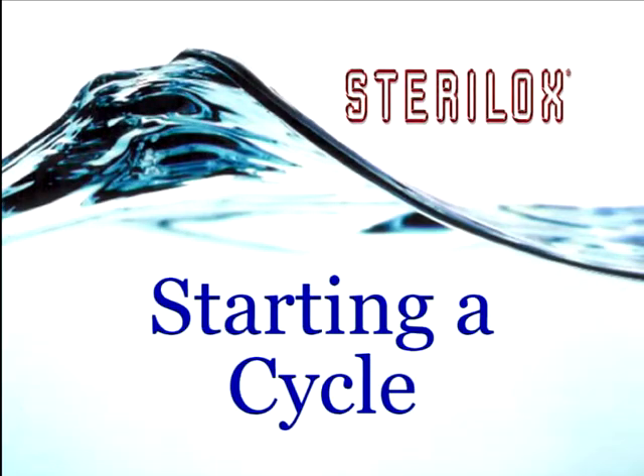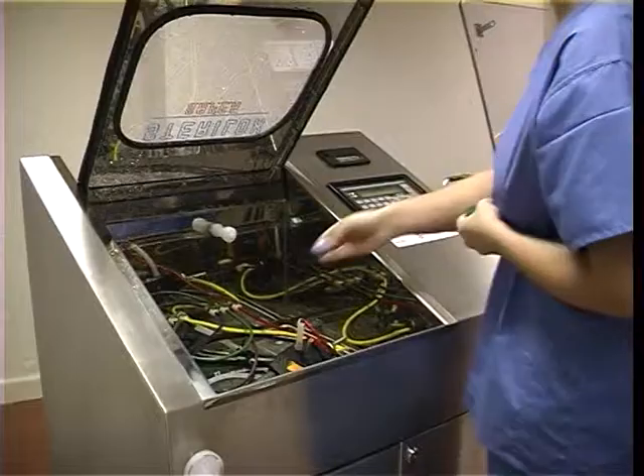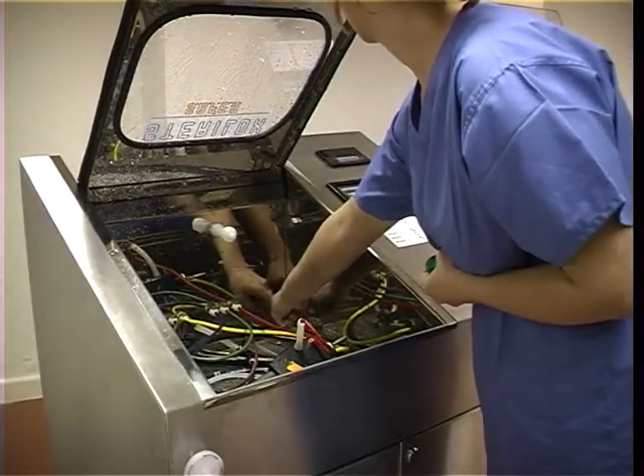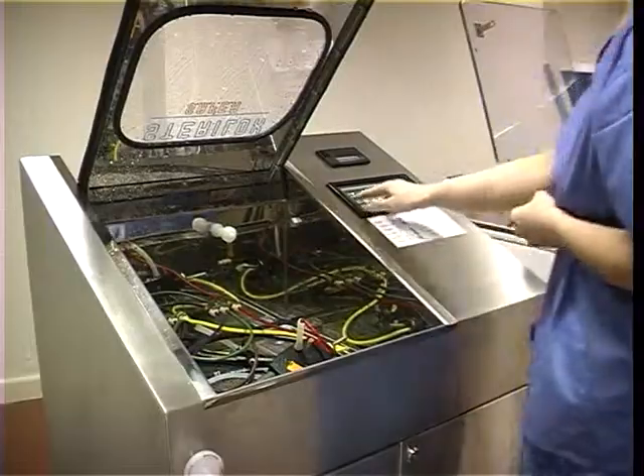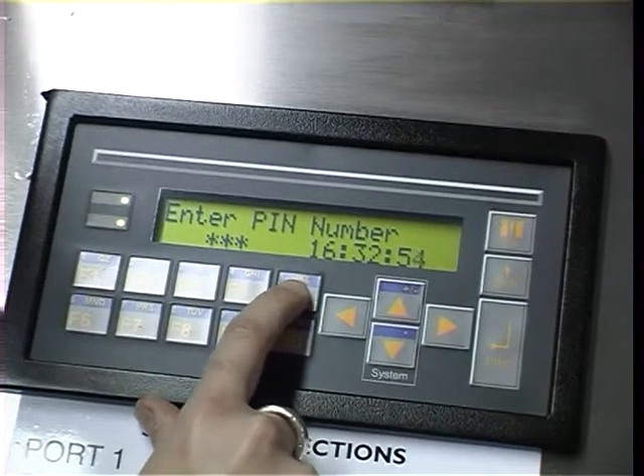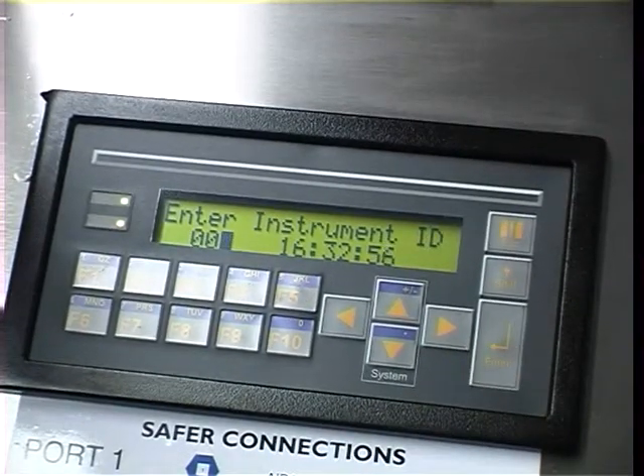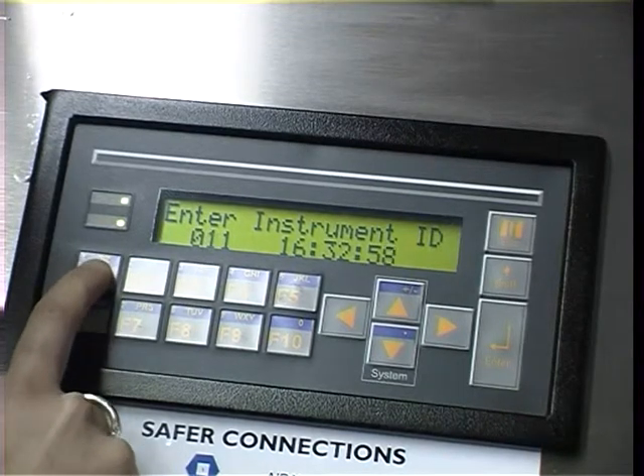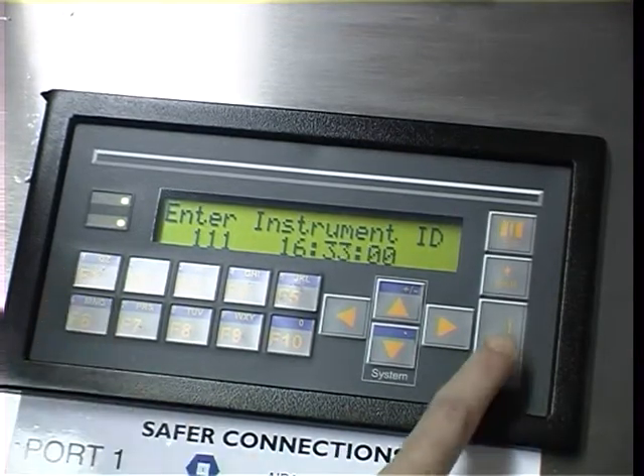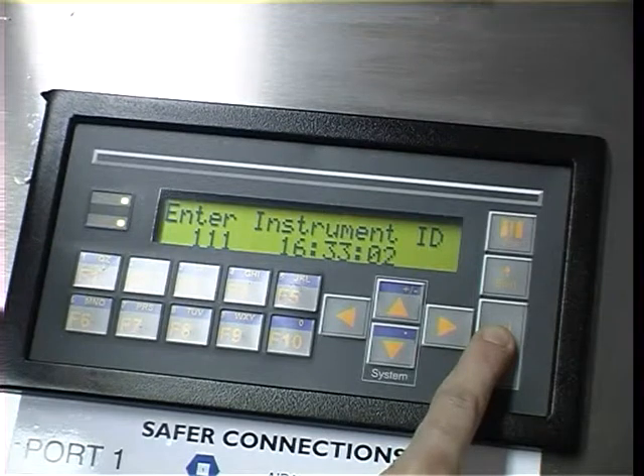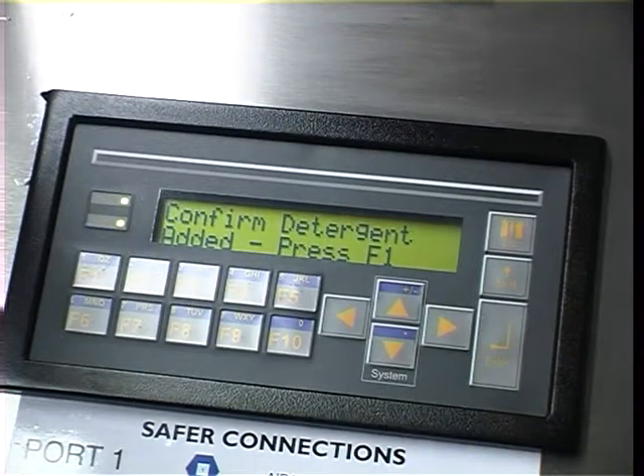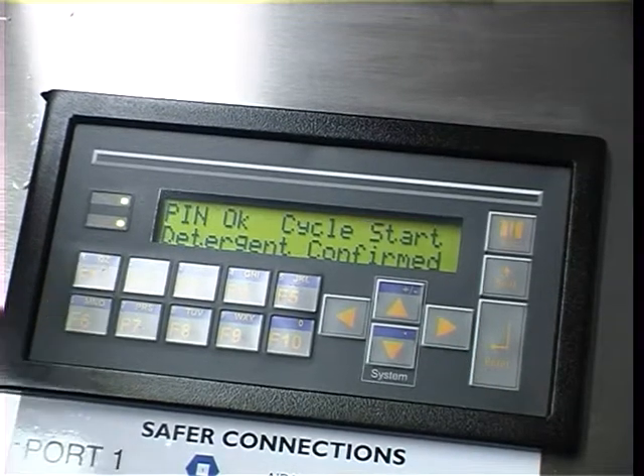Starting a cycle. Place the SSS sachet in the compartment. Put the endoscope into chamber and connect all channels and leak tester. Input your user PIN number, press Enter. Enter the instrument ID number, press Enter. Confirm that detergent has been added, press Enter.